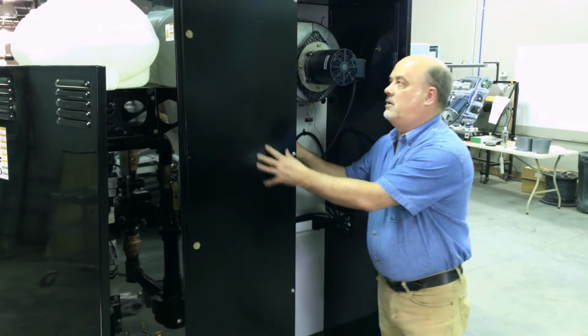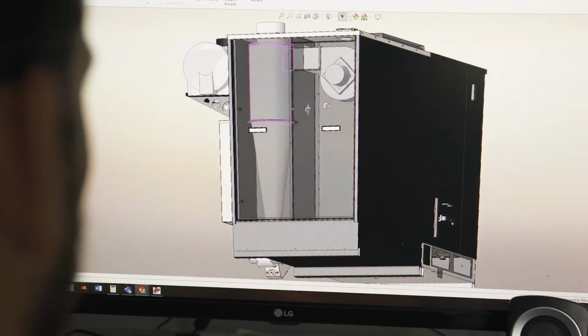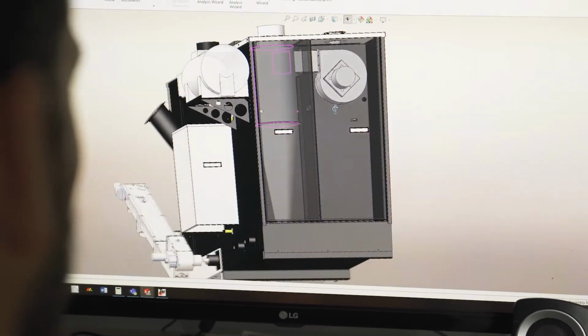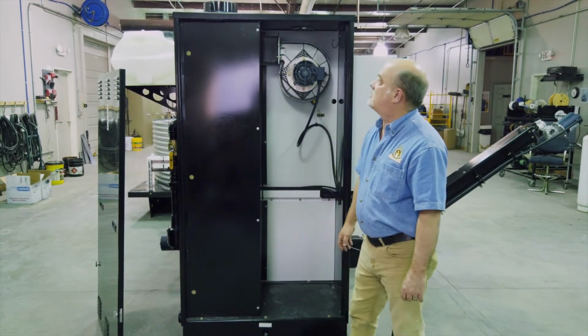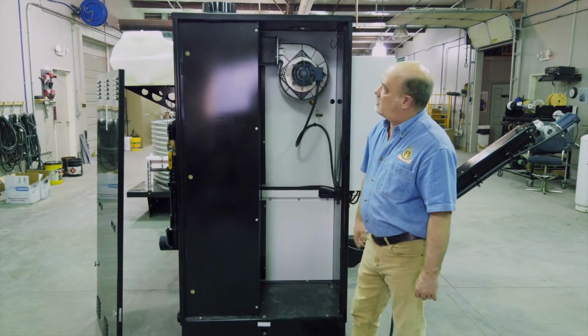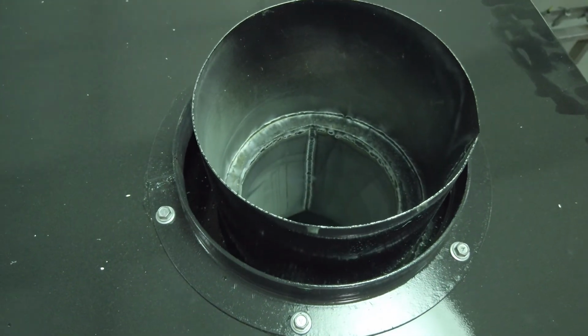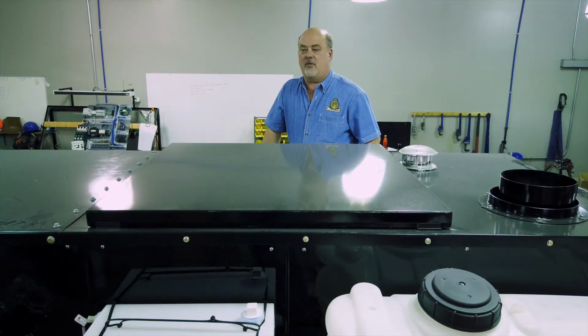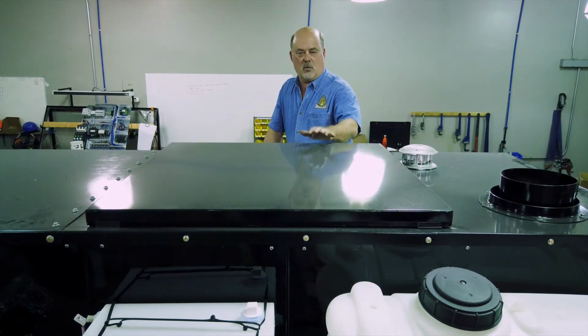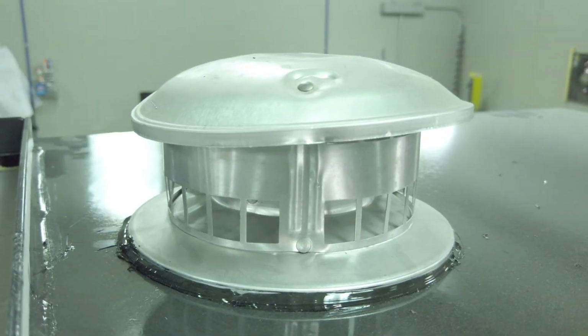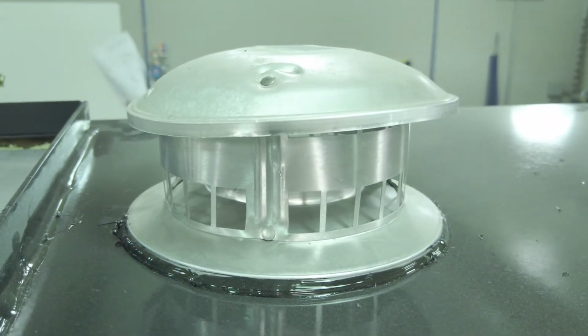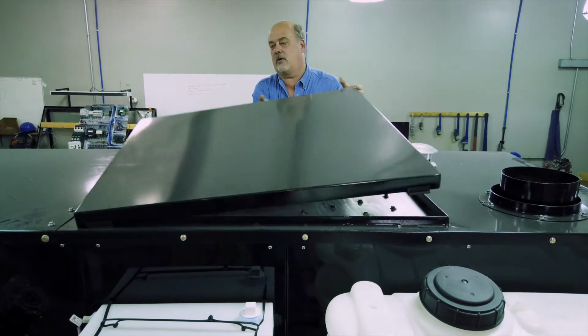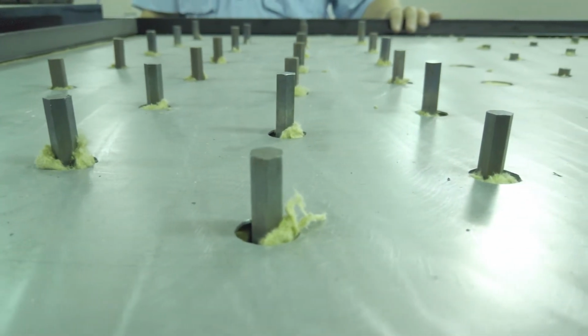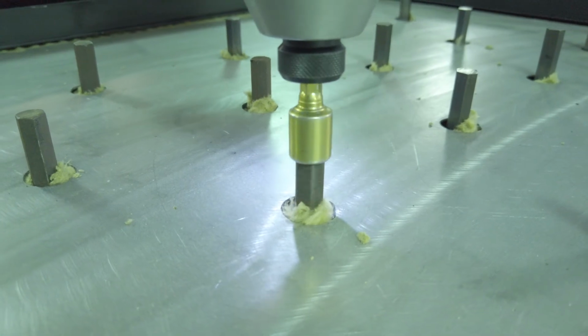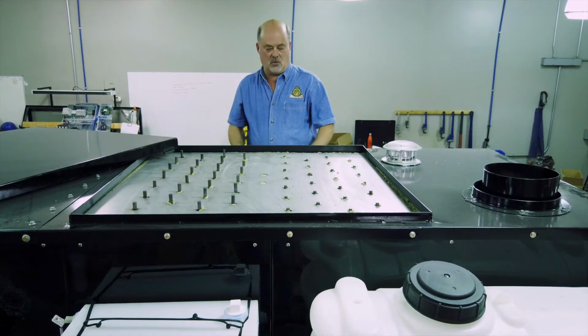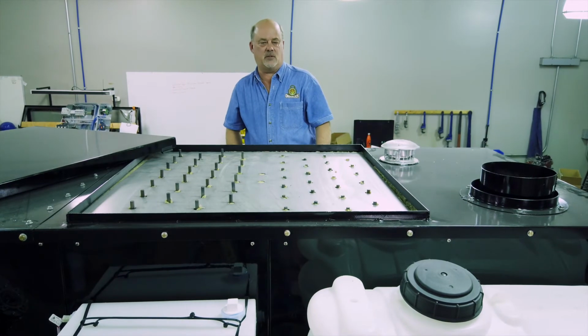Inside here is a Cyclone. It collects the last of the fines that we're capable of collecting and drops it down into a little pit where we empty it from the side. And then it comes out an 8-inch flue pipe up here that can be then vented out according to your local code. All right, here we are on the top of the machine now. We've got a cover plate where the turbulator access to the clean out rods are. Here we have a little vent, take some of the hot gases out. And then under here, you'll see a bunch of turbulator rods where you can twist and turn to actually clean out the insides of your tubes. That'll push ash to the floor, and that's where we clean them out, as we've discussed before.